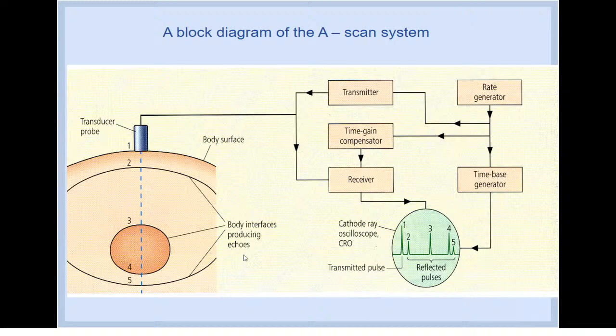Time gain compensator. Due to attenuation of the ultrasound pulses in the body, echoes from deeper interfaces tend to be very weak. These weak signals might contain valuable information.